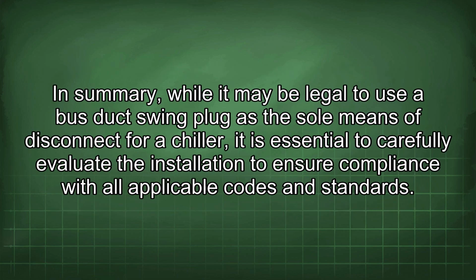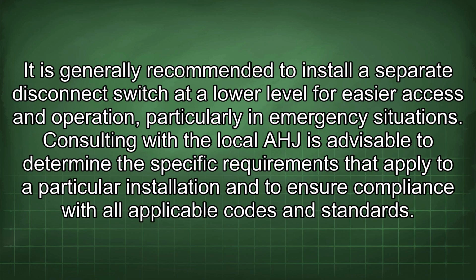In summary, while it may be legal to use a bus duct swing plug as the sole means of disconnect for a chiller, it is essential to carefully evaluate the installation to ensure compliance with all applicable codes and standards. It is generally recommended to install a separate disconnect switch at a lower level for easier access and operation, particularly in emergency situations. Consulting with the local AHJ is advisable to determine the specific requirements that apply to a particular installation and to ensure compliance with all applicable codes and standards.